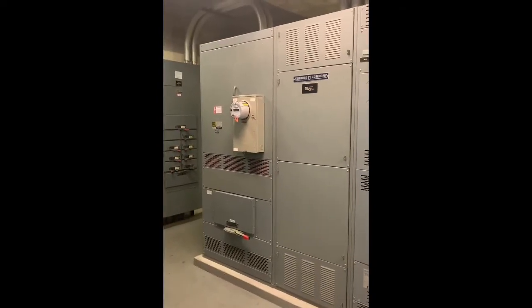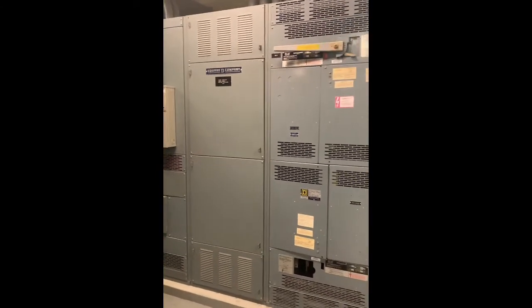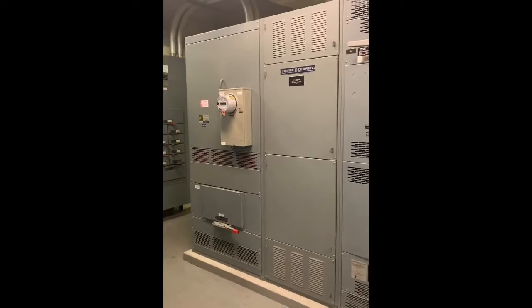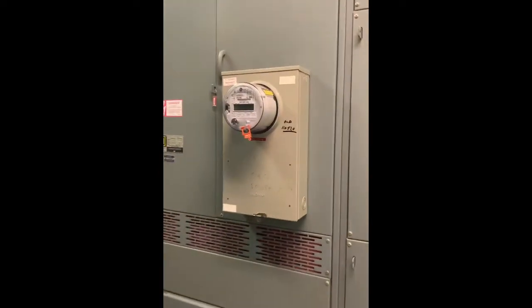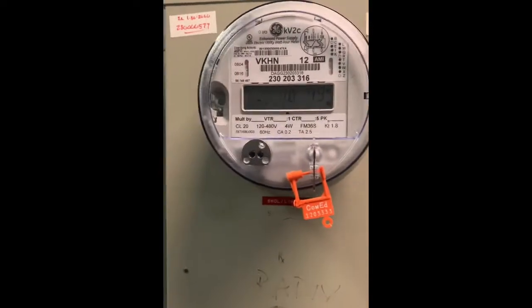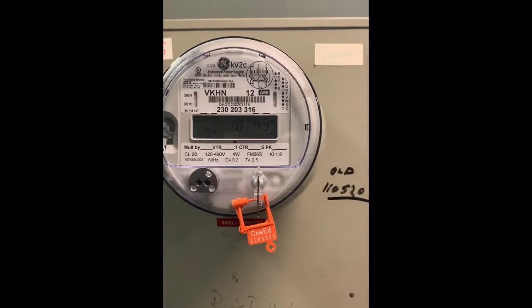All right, switchgear, if you recall, is a high-powered electrical device that will be used to switch or interrupt the circuits in the building's distribution system. A switchboard is a panel or assembly of panels containing switches, meters, buses, and overcurrent protection devices. Now, these two terms are typically used interchangeably. So here we could see a meter for ComEd. This is how they would come in and read the usage. Here is an overcurrent protection device, ground fault.